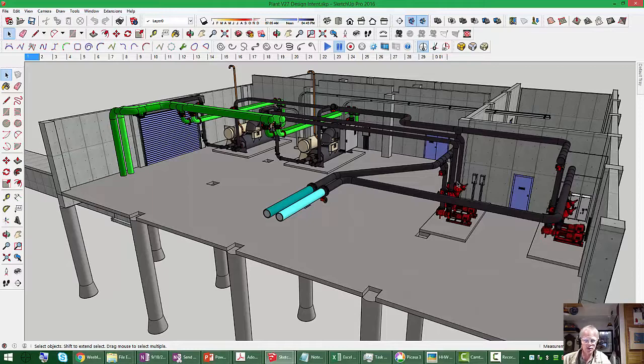To be absolutely sure it was variable flow, you'd want to look at some of the loads. You'd expect the loads in a variable flow plant to have two-way valves on them. There'd be an occasional three-way valve, probably at the end of the mains, to keep flow up, which guarantees a fairly consistent response characteristic, and also keeps the water quality better because flow is constantly running out to the end of the system and back. But by and large, in a plant that's intended to operate as variable flow, most of the loads ought to have two-way valves on them. So you might make a mental note: when I get out to one of the air handling equipment rooms, I'm going to take a look at some of the control valves and see if in fact they're two-way valves.